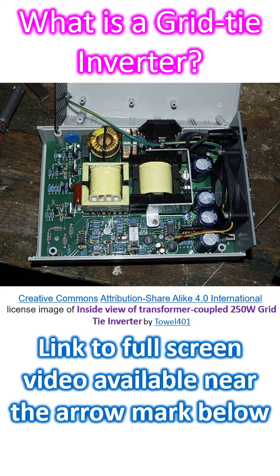Grid tie inverters disconnect quickly from the grid and shut down by design if the grid power is down. This precaution is essential to prevent electricity from the inverter harming persons repairing the power grid.